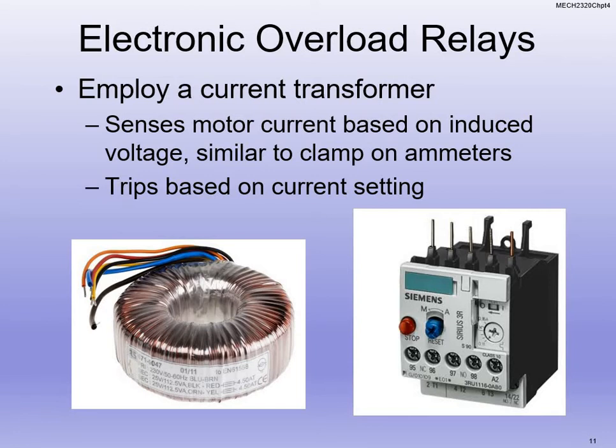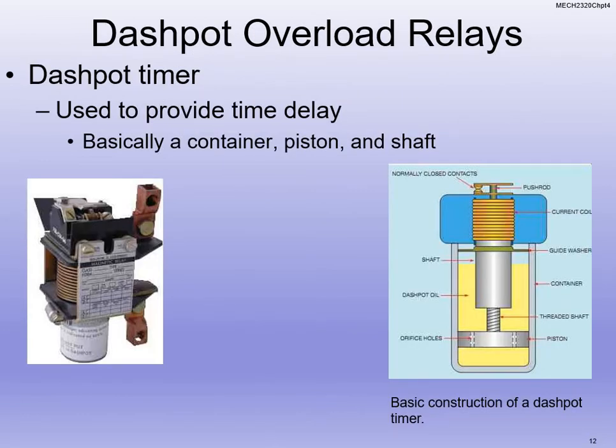You're going to do a lab where you're actually going to trip it on the Future Tech trainer in here. You guys are going to wire it up, and then you're going to dial it in, and adjust the settings so that it actually trips. So you guys will be using a current transformer on that lab to do it. This one's a little bit different. This is a Dashpot Timer.